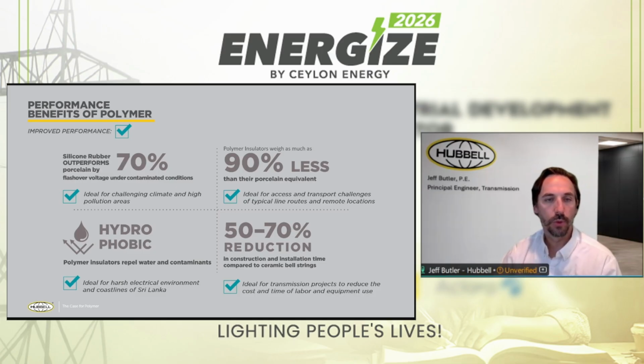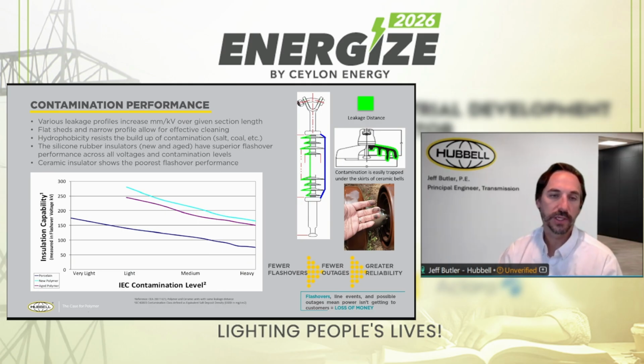So let's go into a little bit more details of what I'm talking about. This was the test, or the study, that we did where we were looking at contamination performance. It may be a little challenging to make out this graph, but the line at the top is a new polymer insulator. The line in the middle is an aged polymer. That meant that we put it through an environmental chamber for the equivalent of 10 years of life. Put it through, I can't recall the exact hours, I think it was 500 hours in a salt fog chamber, but we basically wanted to demonstrate that even not new, a polymer insulator can still perform well, and that speaks to the hydrophobicity breakdown or the aging of the polymer.